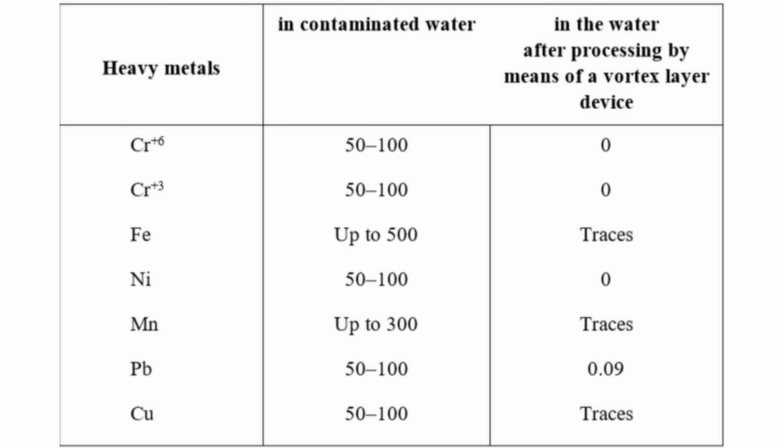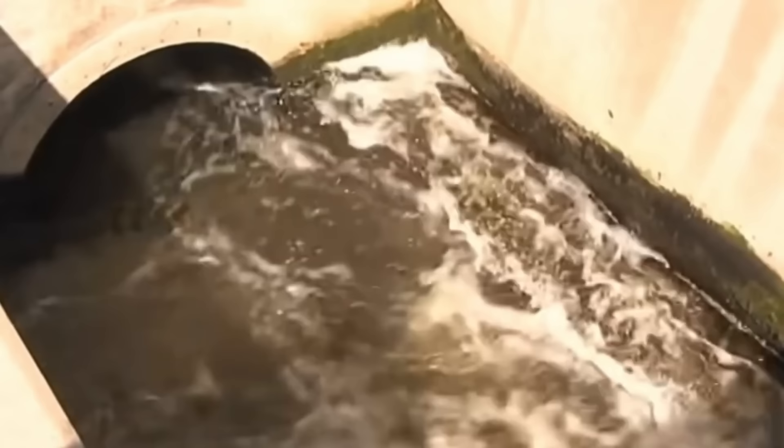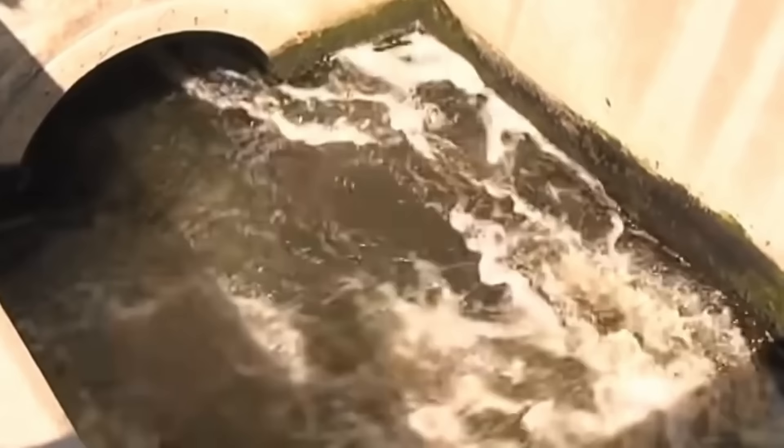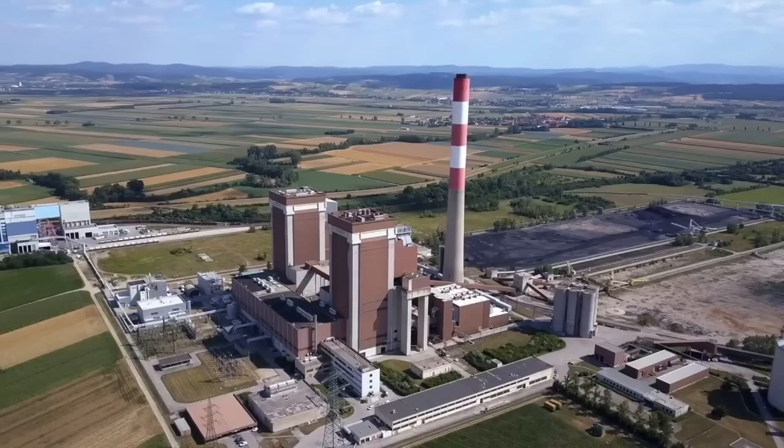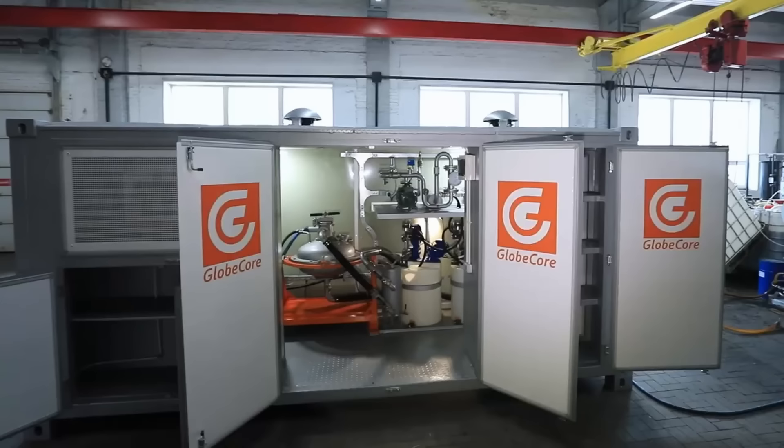As a result, the properties of processed substances change. Furthermore, due to magnetization, solid particles deposit 1.5 to 2 times faster than after treating electroplating industry sewage by other methods. A typical example of electroplating industry sewage treatment by means of AVS is shown in the table.